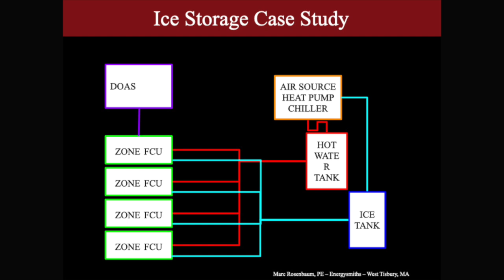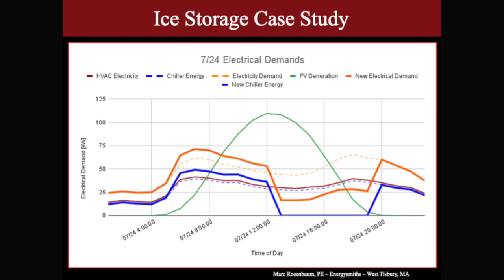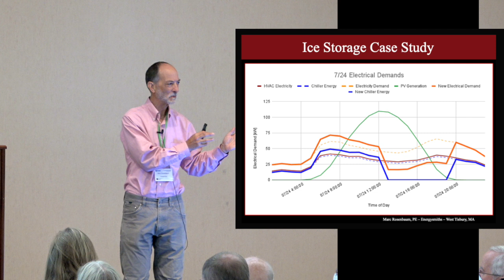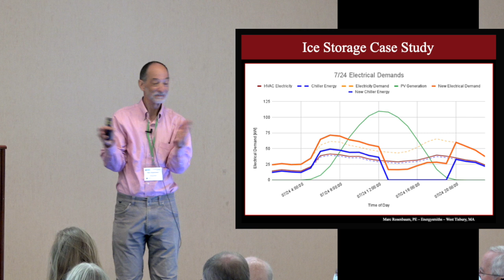In this graph, you see the PV generation. The dotted light line near the top is the conventional electrical demand. The heavy orangey line is the depressed demand from making ice during the day with the PVs in the first part of the day, and then using that ice, the blue line, shutting the chiller off. I think, I didn't get to work with him enough on this, we want to shift this a little to the right, but it shows that this is a viable concept. You could use ice storage to shift load in cooling.